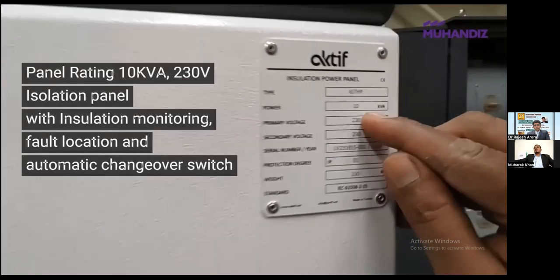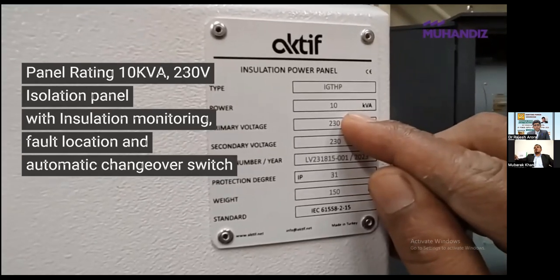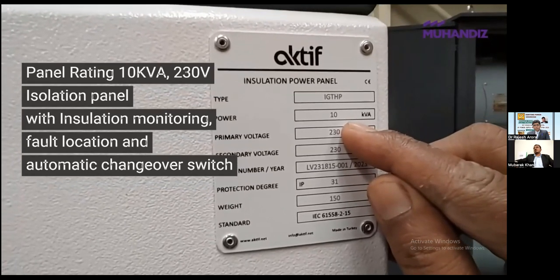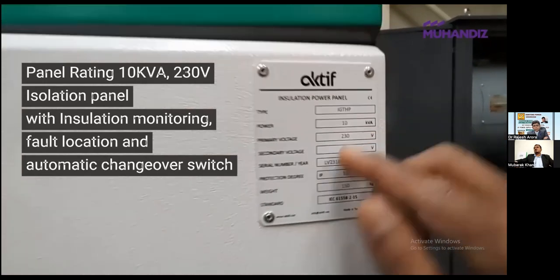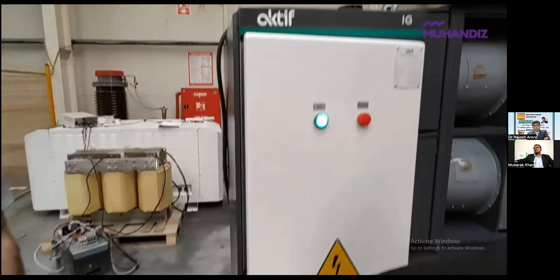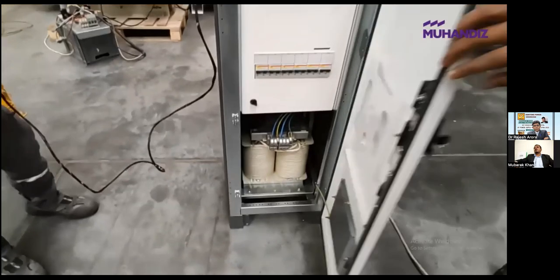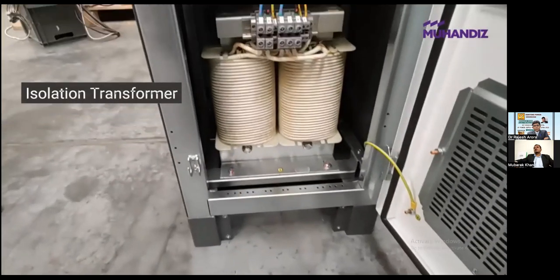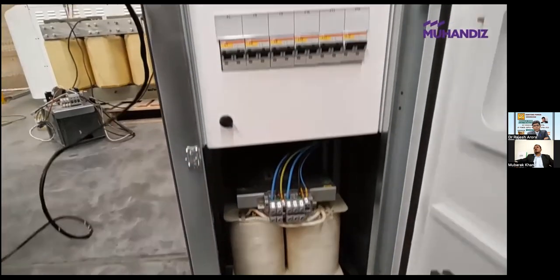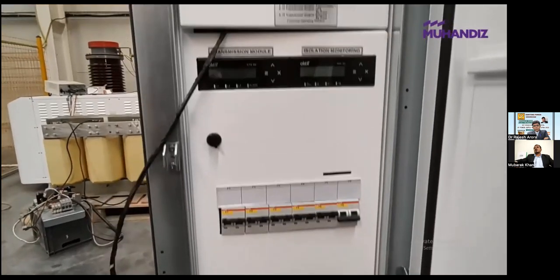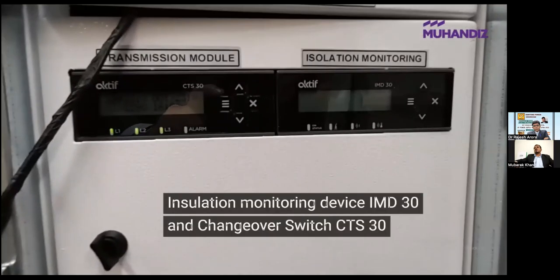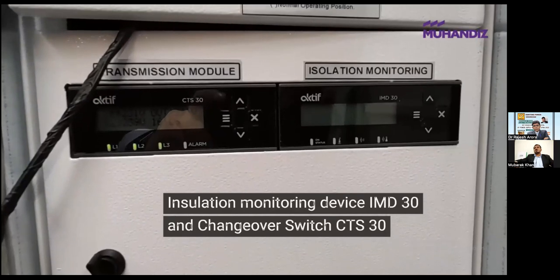So the panel rating here is 10 kVA with insulation monitoring device, fault location, and automatic changeover switch. This is the type of panel which we are using here. This is a video which I recorded when I visited the factory. So this is the isolation transformer. We have the insulation monitoring device and changeover switch CTS 30.